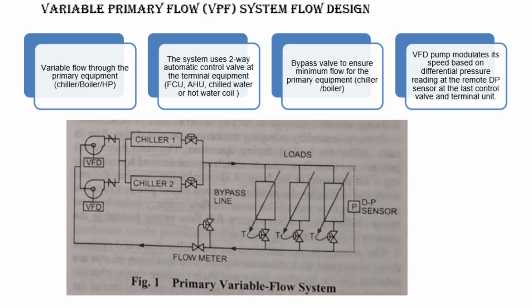It monitors the pressure difference between supply and return lines. The VFD pump then adjusts its speed automatically to maintain the desired differential pressure, ensuring that just enough water is circulated to meet the load. No more, no less. This setup eliminates the need for a secondary pumping loop, reduces pumping energy, and improves overall plant efficiency. The flow meter in the return line helps monitor total system performance and verify chiller or boiler loading.